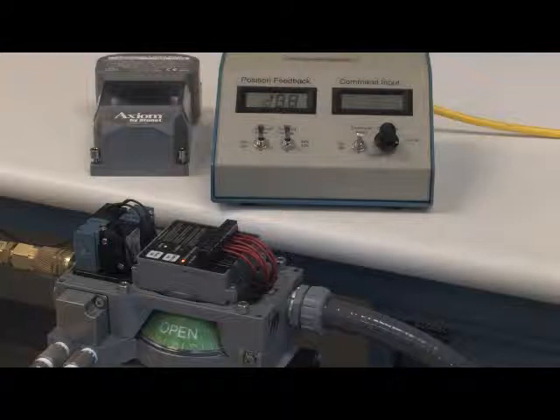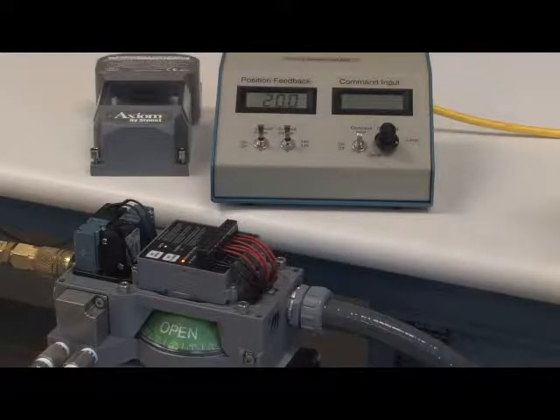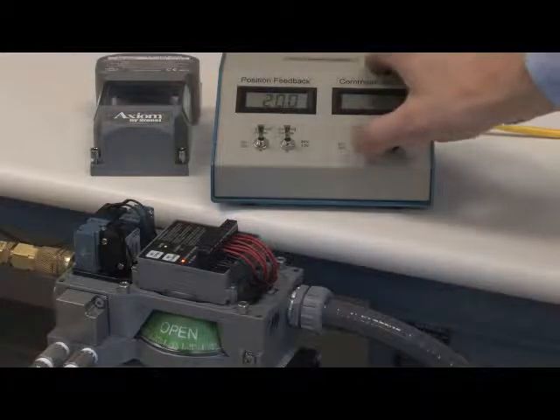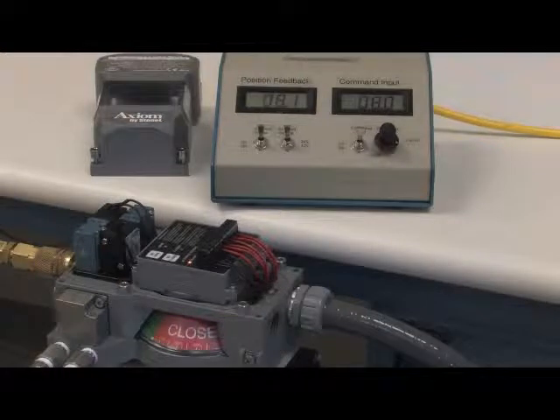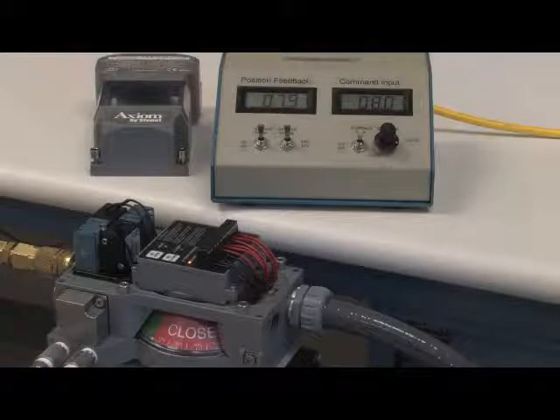Now, with the main solenoids energized, we'll energize the command input, which is set at 8 milliamps. And it'll go within plus or minus 3 degrees, or plus or minus 4 percent, of the command input signal.